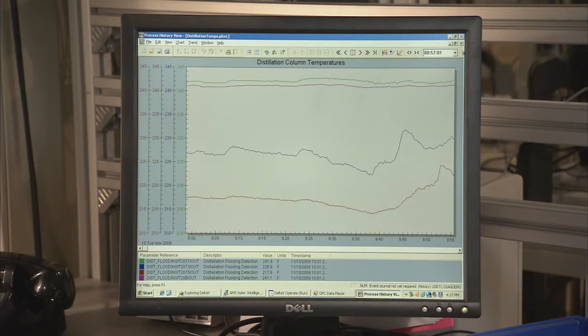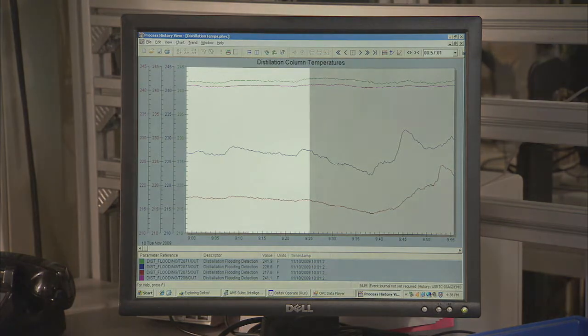Temperature measurements made across the packing have traditionally been used as a method to detect flooding. This chart here shows a temperature response under normal conditions in which there is clear separation in the column. The same response is seen just prior to flooding.